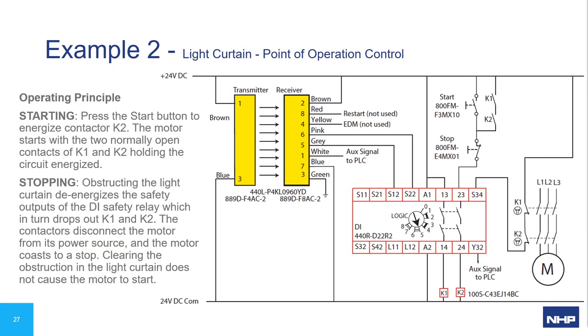In the second example, a light curtain transmitter and receiver powered by 24 V DC have two solid-state outputs going into a GSR DI monitoring relay. The relay outputs control the coils of two safety contactors that isolate the motor, with mechanically linked contacts on the contactors feeding back to the safety relay to confirm they opened on demand. To start, press the start button to energize contactor K2; the motor starts with the normally open contacts of K1 and K2 holding the circuit. Obstructing the light curtain de-energizes the DI relay outputs, dropping out K1 and K2, and the motor coasts to a stop. Clearing the obstruction does not cause the motor to restart — you must press the start button again.